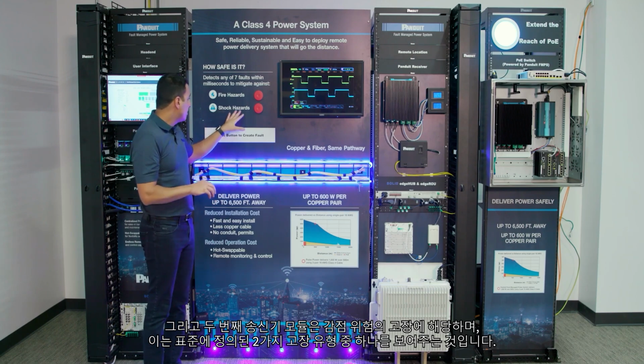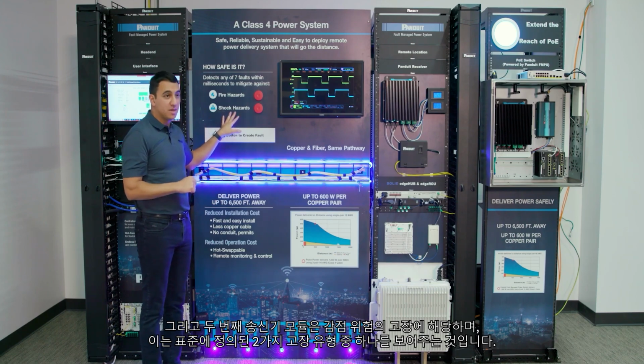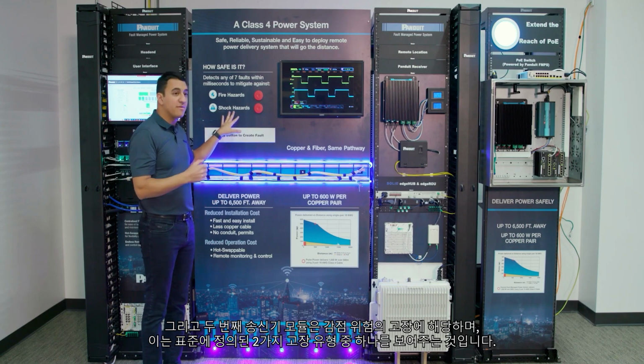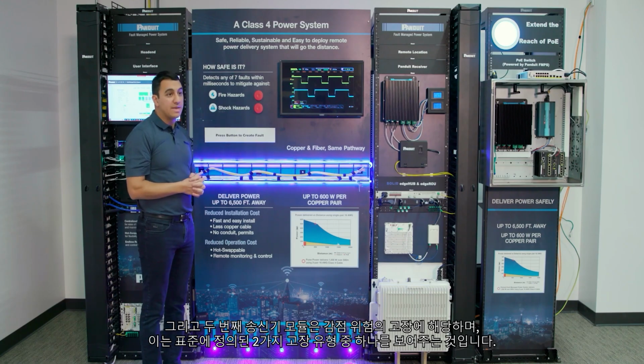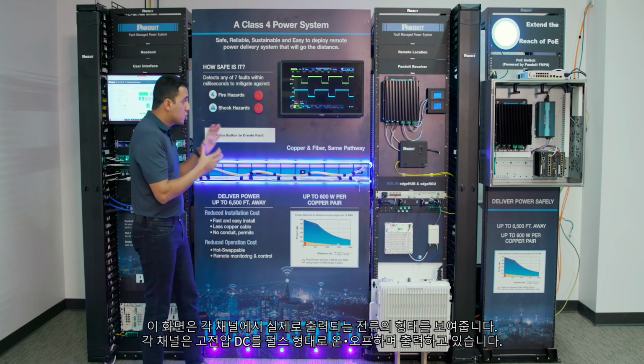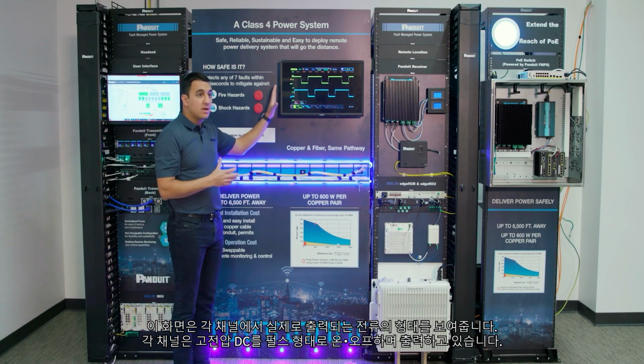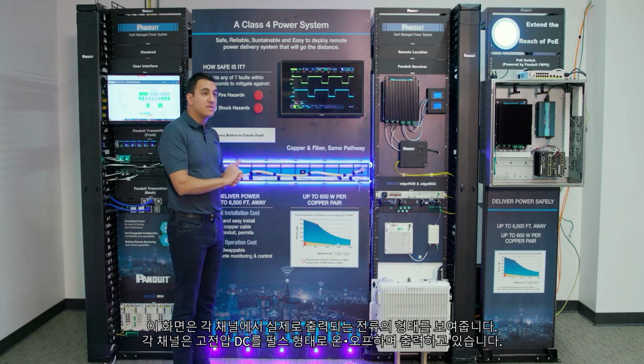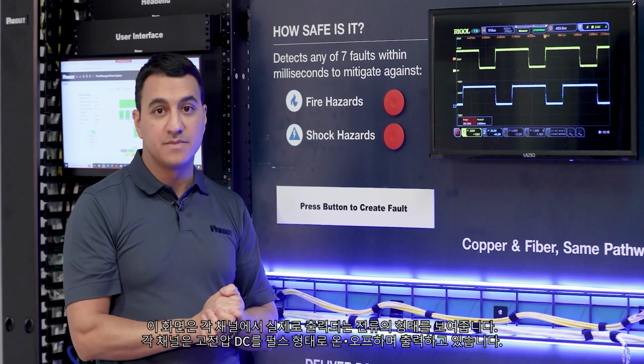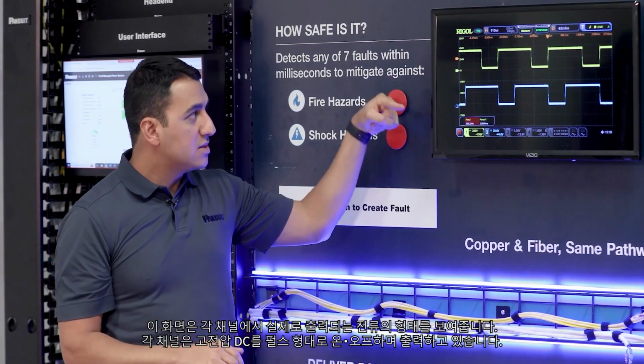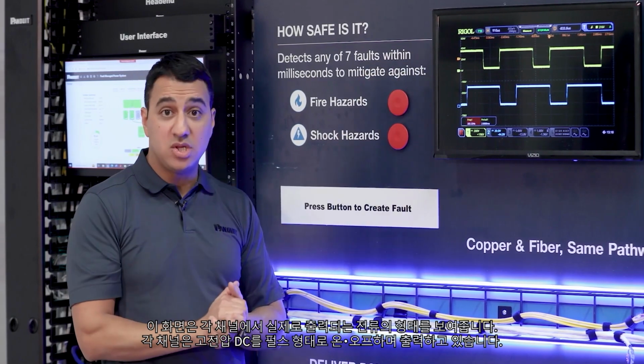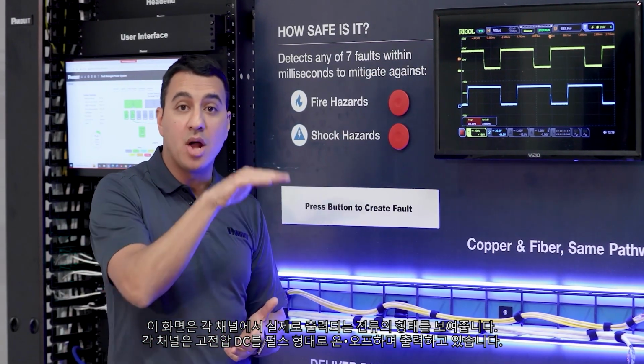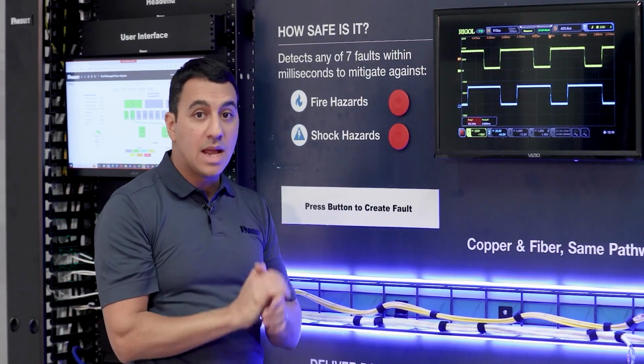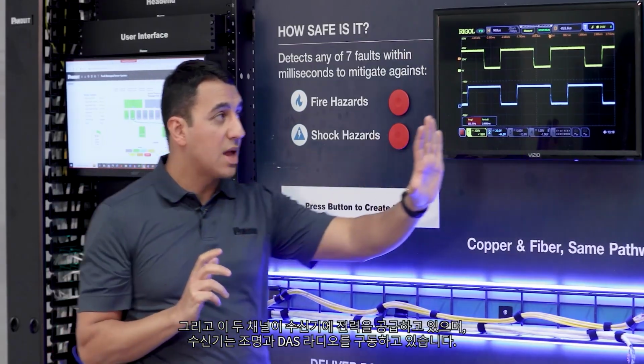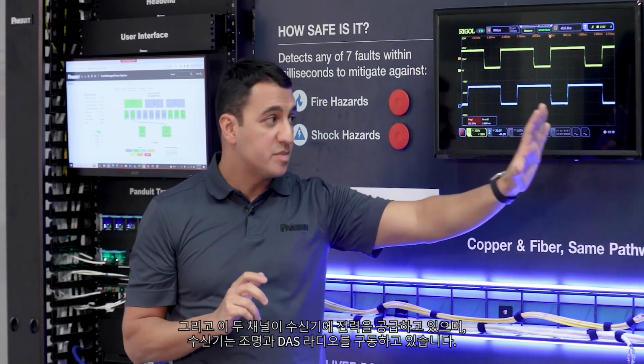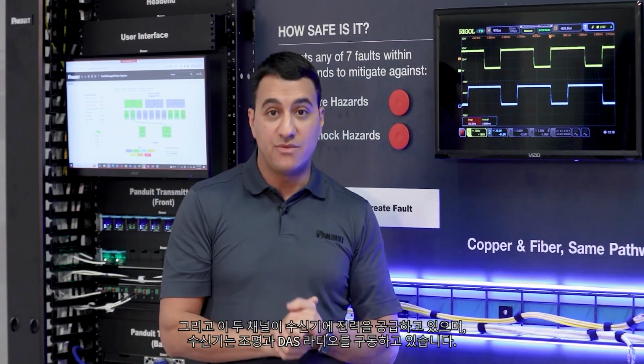And the second transmitter module is connected to a shock hazard, which represents one of the 2 faults that are in the standard. And we're showing you through this screen here what the actual shape of the current is that's coming out of these channels. Each one of these channels is outputting this high voltage DC that is being pulsed on and off. Again, these 2 channels are powering our receiver, which is powering the lights and the DAS radio for us.